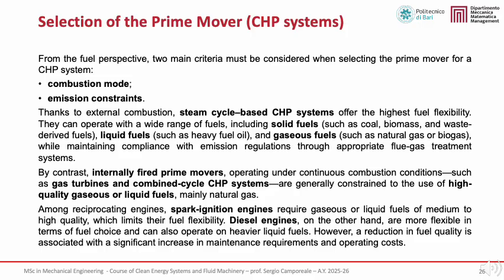By contrast, internally fired prime movers, such as gas turbines and combined cycle CHP systems, operate under continuous combustion conditions and are typically limited to high-quality fuels, mainly natural gas. Among reciprocating engines, spark ignition engines require gaseous or liquid fuels of medium to high quality, whereas diesel engines are more fuel flexible and can also operate on heavier liquid fuels. However, lower fuel quality generally leads to higher maintenance requirements and operating costs. These considerations show how fuel characteristics and emission constraints strongly influence the choice of the prime mover in CHP applications.